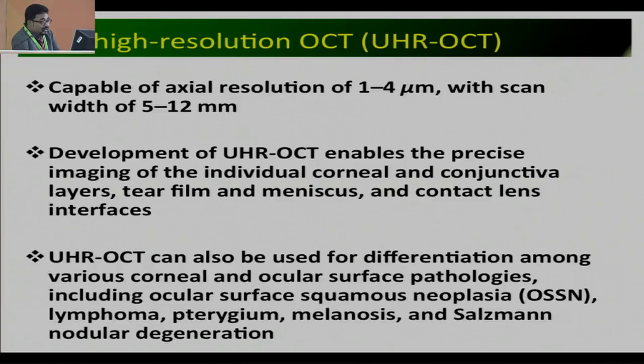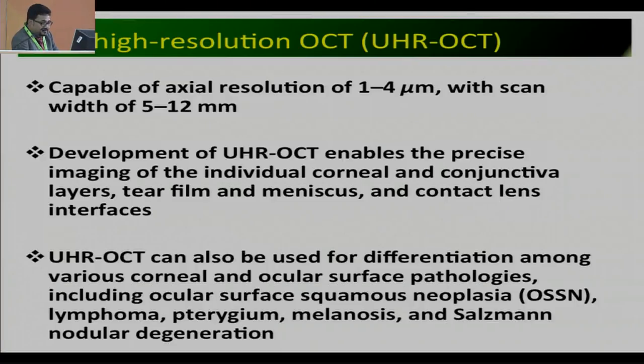Recently, there is ultra-high resolution OCT, which is capable of axial resolution of 1 to 4 microns and can image widths of 5 to 12 millimeters. Development of ultra-high resolution OCT enables precise imaging of individual corneal and conjunctival layers, tear film and meniscus, and contact lens interfaces. UHR OCT can also be used to differentiate among various corneal and ocular surface pathologies including ocular surface squamous neoplasia, lymphoma, pterygium, melanosis, and Salzmann nodular degeneration.